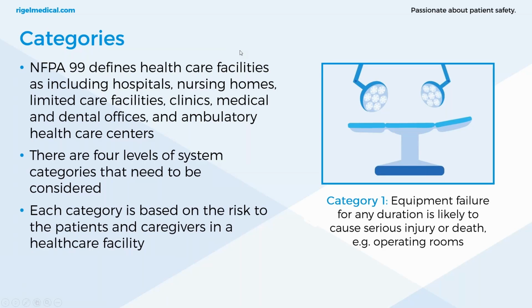There are 4 levels of system categories that need to be considered, and each category is based on the risk to the patients and caregivers in a facility, in any healthcare facility. Now, it's ultimately up to the facility to decide which categories the equipment falls under, and this is done via risk assessment, but the categories are typically classified that way.